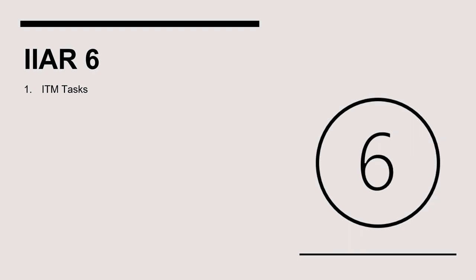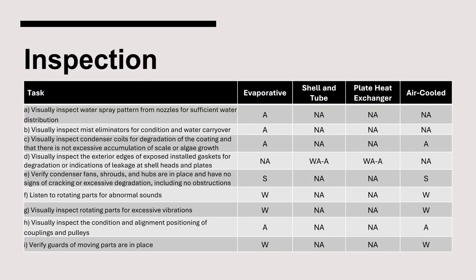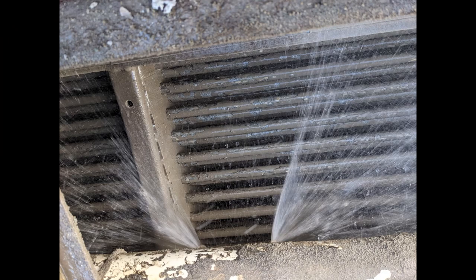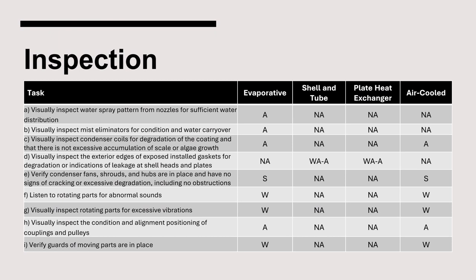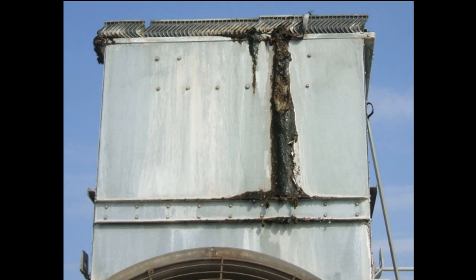Now let's turn our attention to the Inspection, Testing, and Maintenance requirements for condensers, contained in Chapter 8 of IIAR Standard 6. The ITM Table in Chapter 8 relates to evaporative, shell and tube, plate heat exchanger, and air-cooled condensers. The first inspection task requires visually inspecting the water spray pattern for sufficient water distribution on an annual basis for evaporative condensers. The spray nozzles are located above the condenser coil and spray down onto the coils containing ammonia. For forced draft evaporative condensers, the mist eliminators can be removed in order to view the spray nozzles. Condenser mist eliminators must be visually inspected on an annual basis. Here are some examples of mist eliminators that are in poor condition and must be cleaned or replaced.